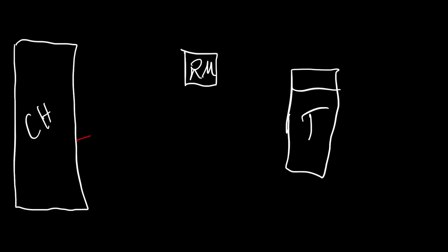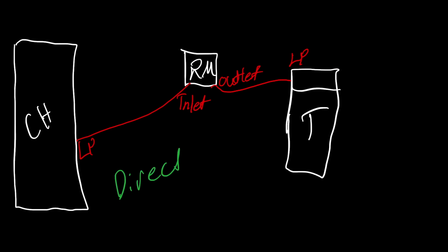Now, the other method is your direct recovery, where you're just going straight from chiller to recovery machine, out of recovery machine into the tank. Even with a push-pull, you're still going to have direct recovery when you get to the vapor side of it. So once you've gotten all the liquid out of the system and it's just strictly vapor, then that's it. And you'll know because on the last tank you're working on, as you're doing the push-pull, you'll see the weight on the scale go up, up, up, up, and then just dead stop.